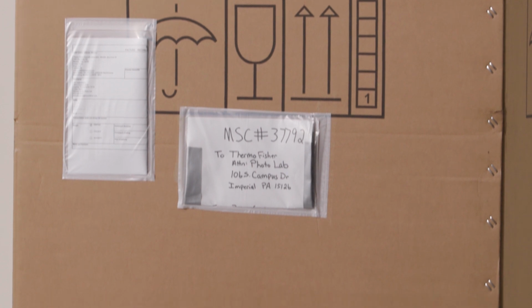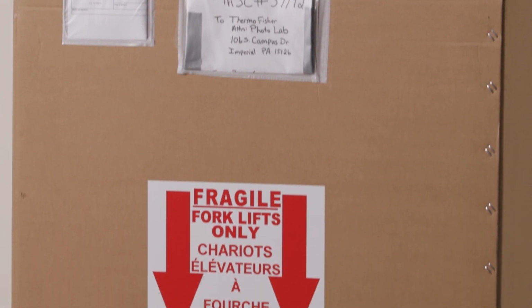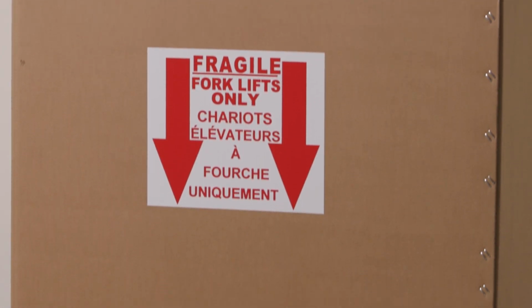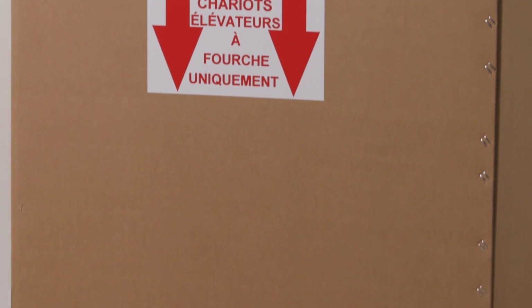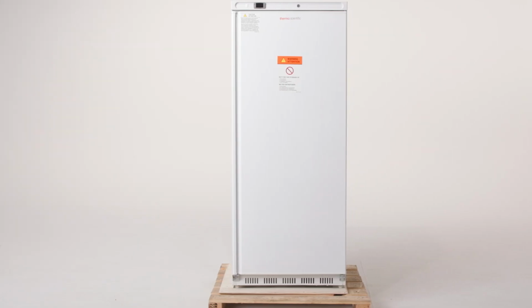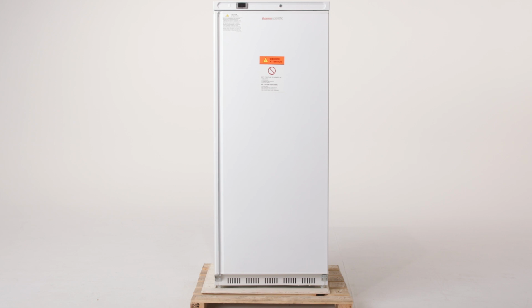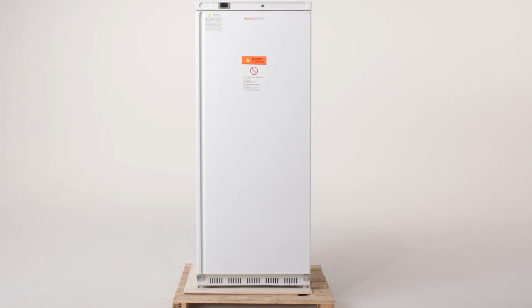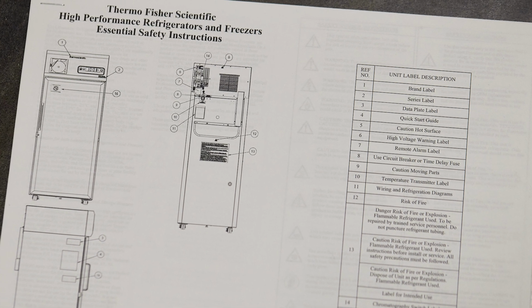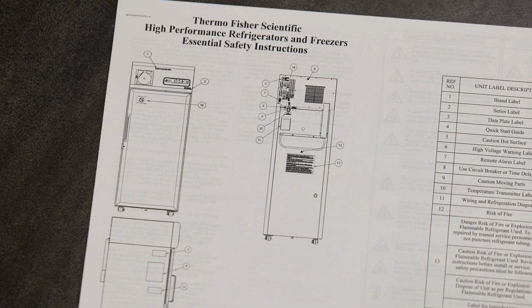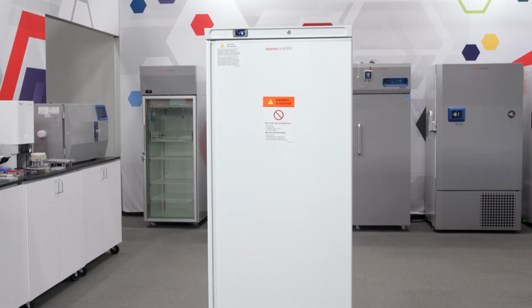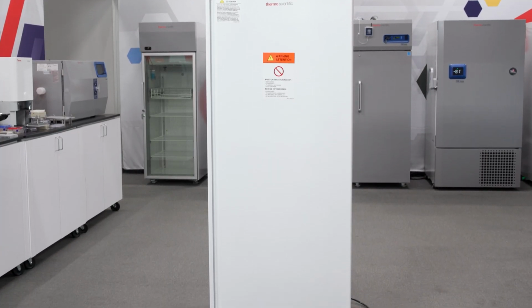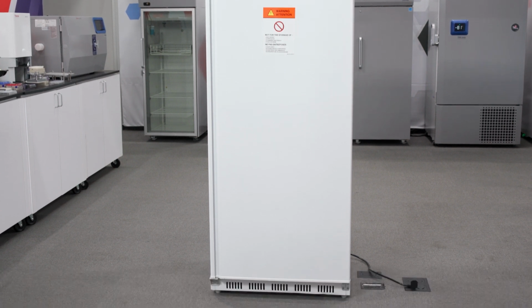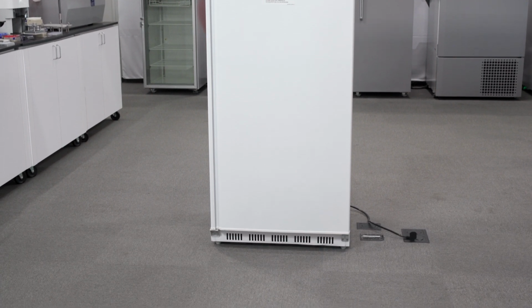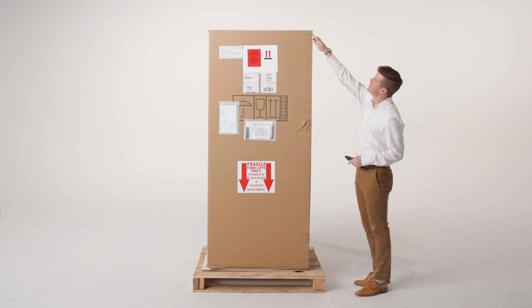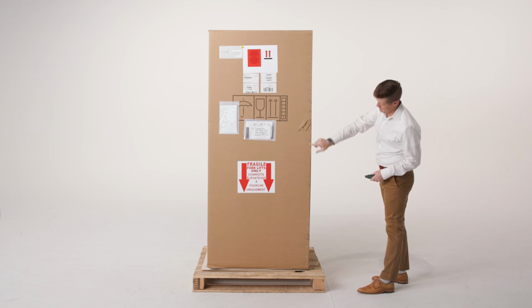Prior to removal of the exterior packaging, ensure you have moved your unit to the location in immediate proximity to the intended area of use. This will help you prevent any damages that may occur in transporting the unit inside of your facility. Check the user manual for recommendations in selecting a location for use. Choose a location that provides a clearance of 12 inches at the top, 2 inches at the rear, and 2 inches on each side.